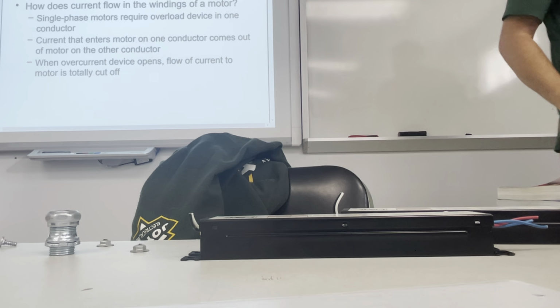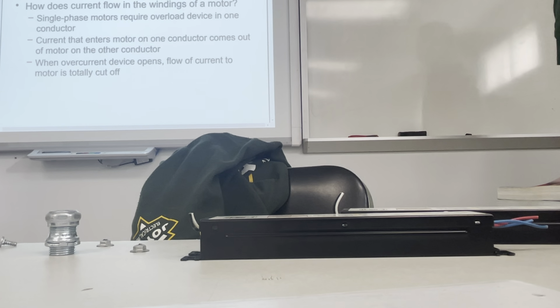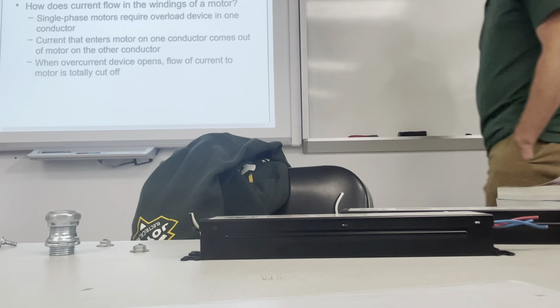How does current flow in the windings of a motor? Single-phase motors require an overload device in one conductor. Current that enters the motor on one conductor comes out of the motor on the other conductor. When the overcurrent device opens, the flow of current to the motor is totally cut off.